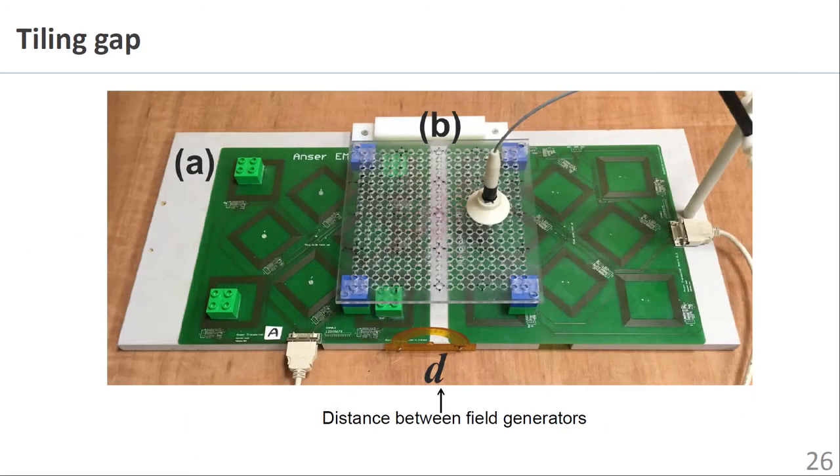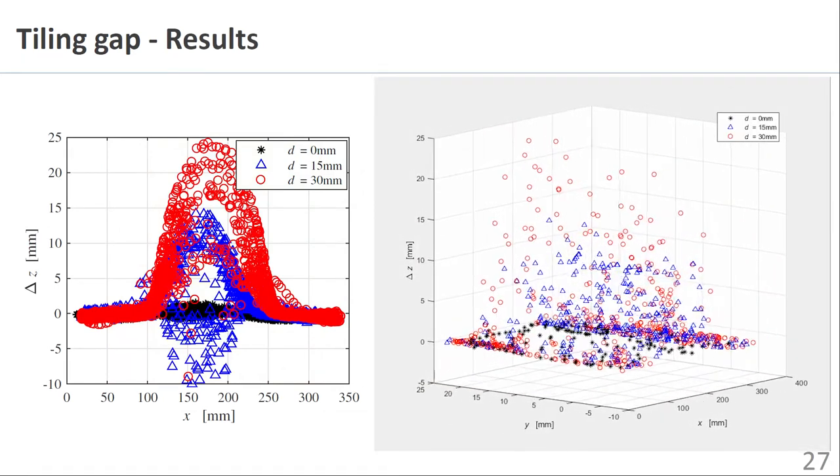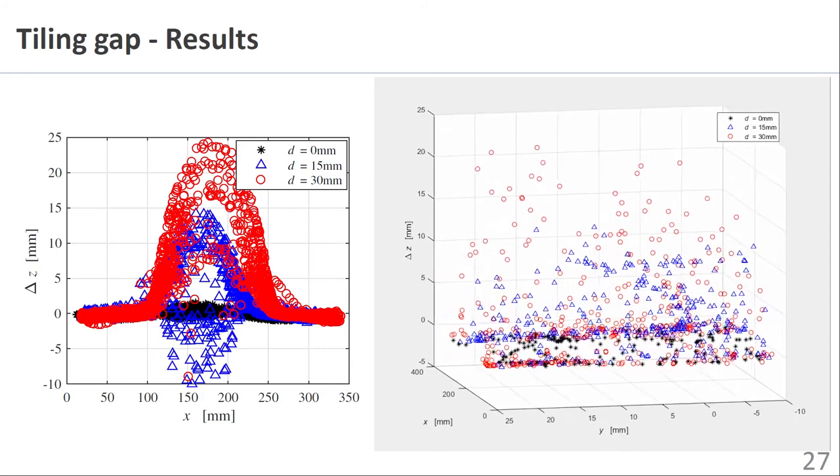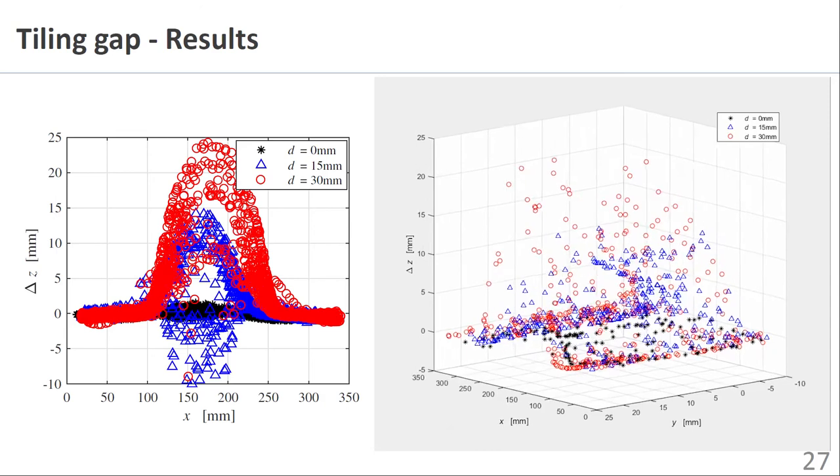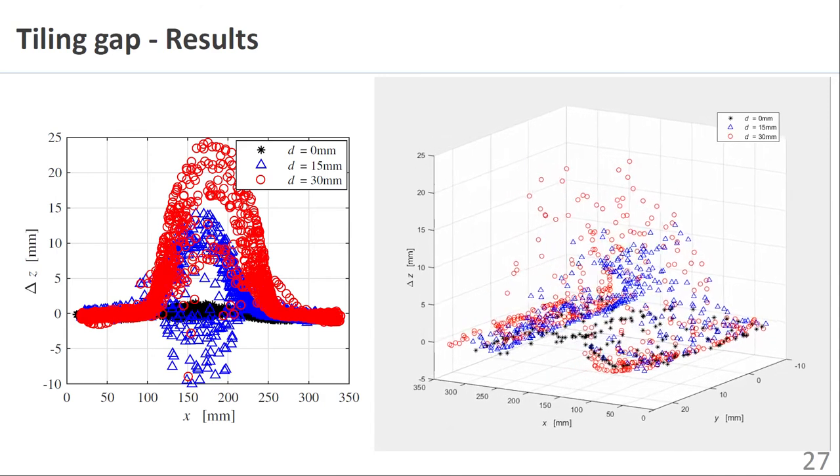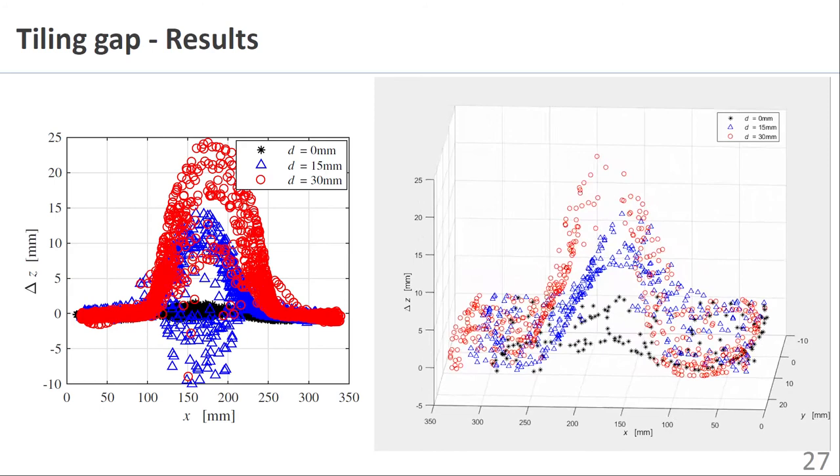An experiment was also performed to establish whether sparse placement of adjacent field generators is feasible. A known separation, D, was introduced between two adjacent field generators A and B. A cloud of points was acquired at a fixed height above the field generators above the separation. This resulted in the magnetic sensor reporting errors which were maximized in the region of the separation as shown. Observing the z-axis only, errors in excess of 10 mm are observed for separations as small as 15 mm between the field generators.